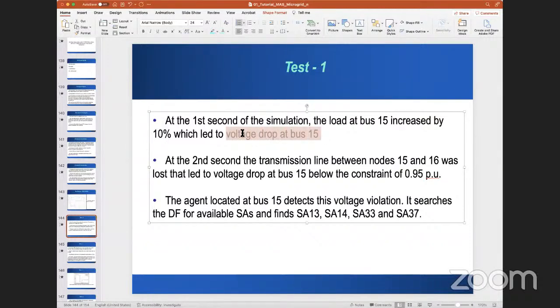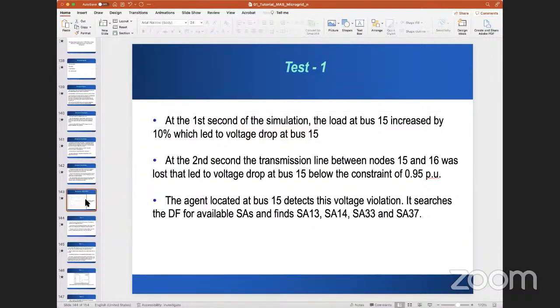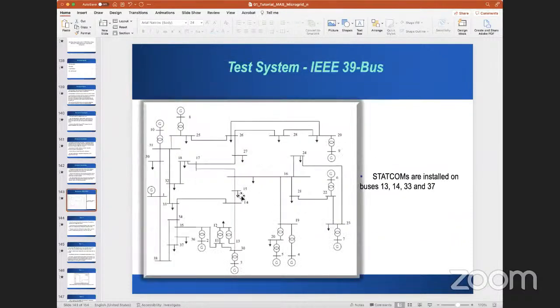When we increase the load here, the voltage goes down—that's generally the case, when you increase load the voltage will drop a little bit, but it's not violating yet. But when this line is removed for whatever reason, now you have the violation—the voltage here goes below 0.95.